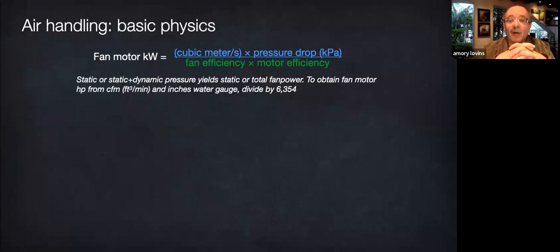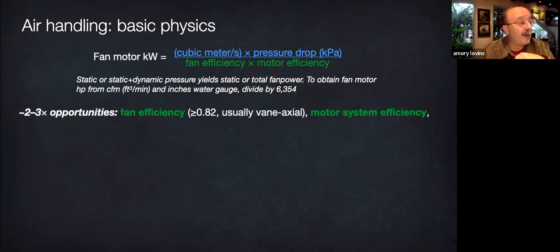Now, if you do need to move air, but you can't do it passively, here's some basic physics to bear in mind. The power used by a fan is the product of its flow times the pressure head it works into, the friction it must overcome, all divided by the product of the efficiencies of the fan and the motor. Notice that the fan and motor systems together typically offer about 2 or 3-fold efficiency gains. I need to update that number. As you'll see later, the fans are better now.